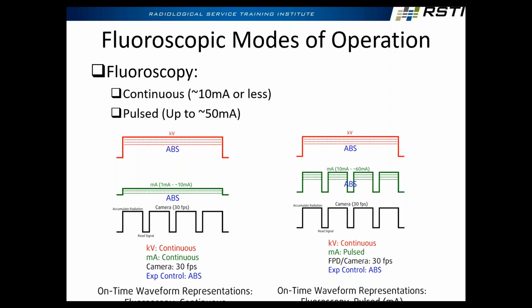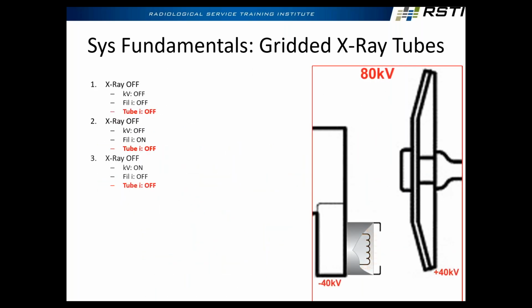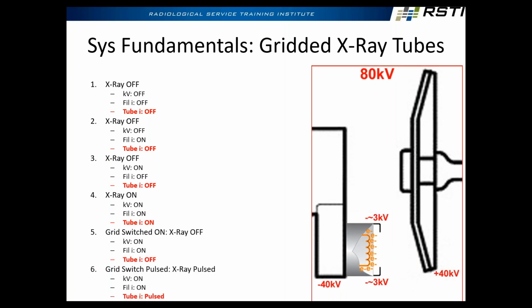What we're doing now, though, with modern systems is pulsing the MA to match the detector. So we're only giving radiation at the exact same time the camera, or the detector in this case, is pulsing. And this slide here, that's what this is talking about. Again, this is a little in the weeds here, but on cath lab systems and CTs, they will apply a 3 kV bias voltage to these pins right here, negative 3 kV. So now these pins are at negative 43 kV. What's that going to do? When I turn that 3 kV on, it's going to stop that electron flow, because electrons want to flow from negative to positive, but now this area is more negative. So I can actually stop the tube current by turning this 3 kV on and off.